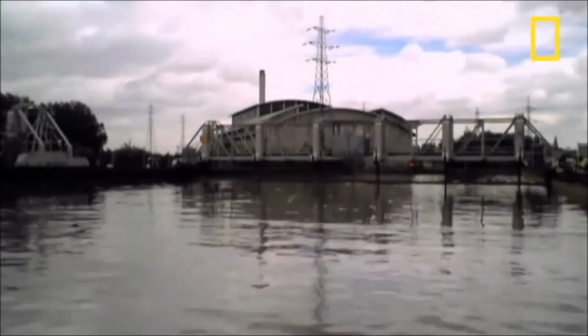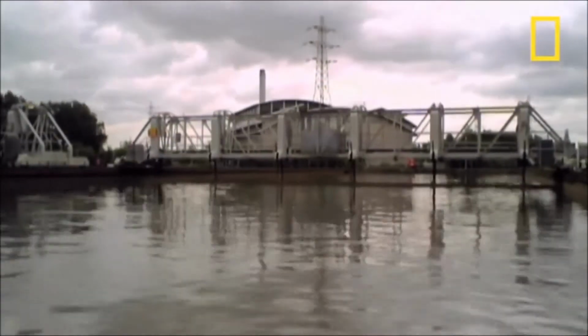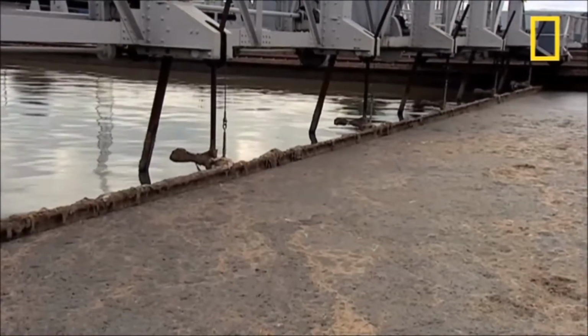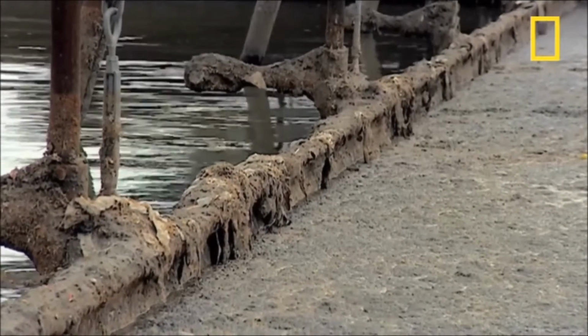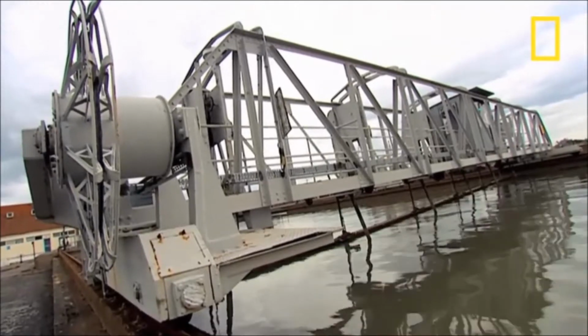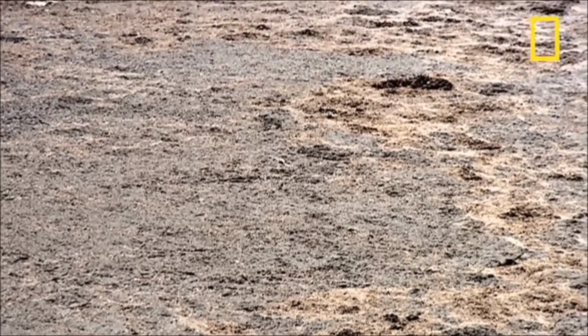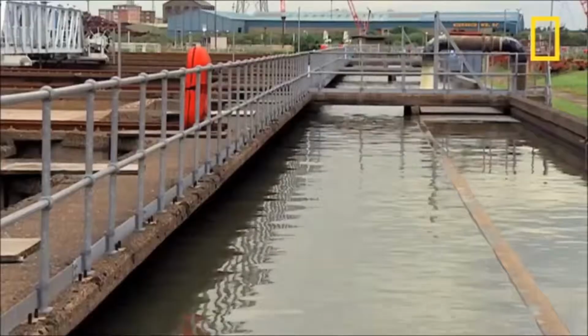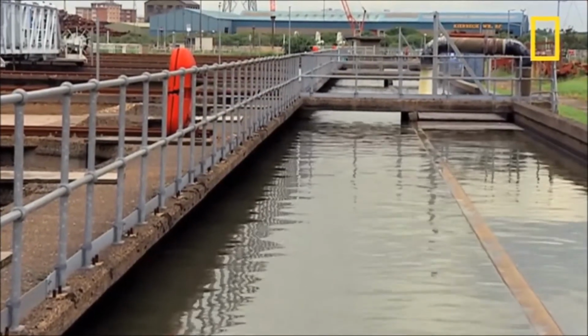Over the top of each tank is a moving bridge, which has 2 blades to remove solid organic material from the sewage. The top blade skims scum from the surface, while a second submerged blade dredges the heavier settled sludge from the bottom of the tank. All this solid sludge is then sent for further processing. The remaining sewage then flows down this way towards the secondary biological treatment process.